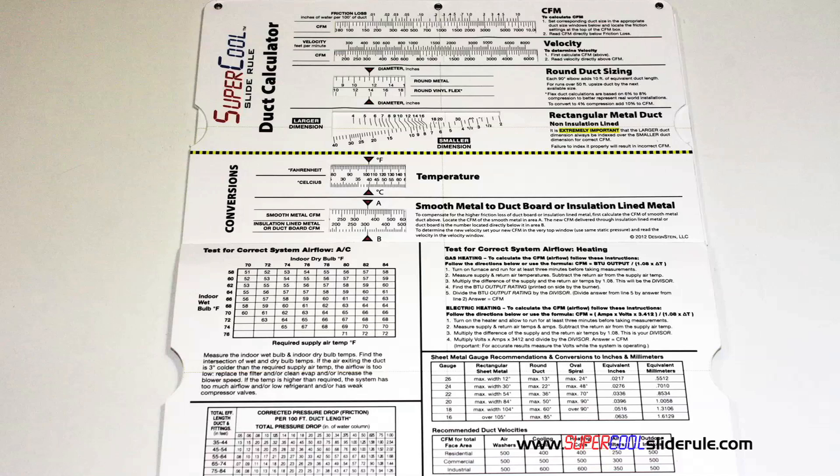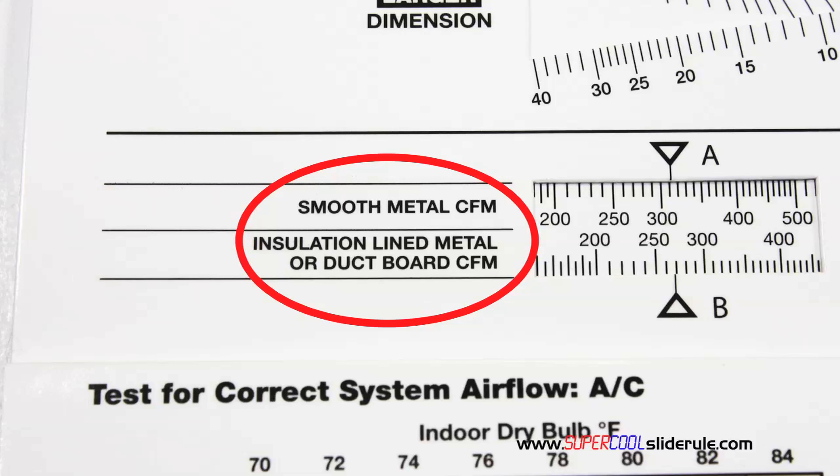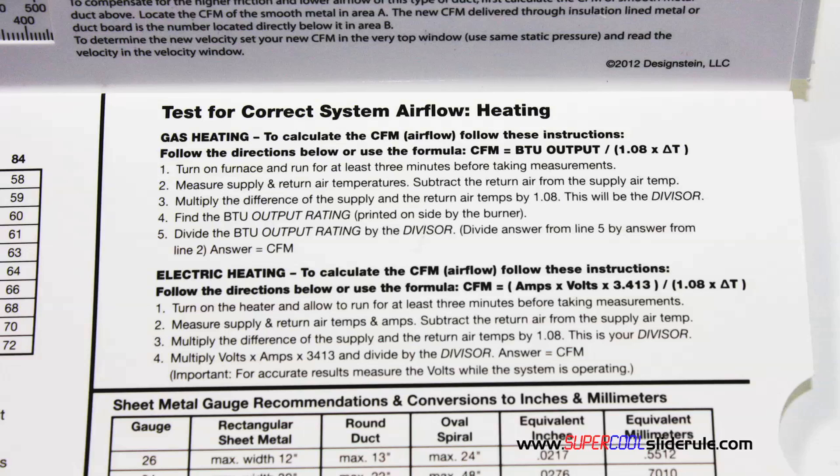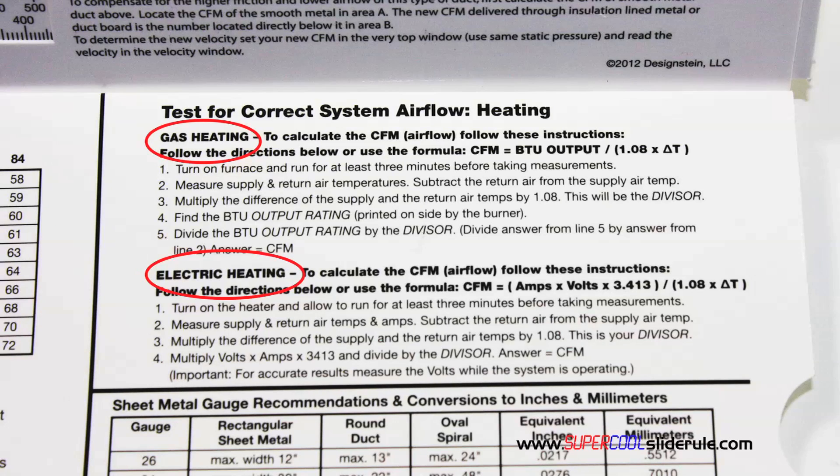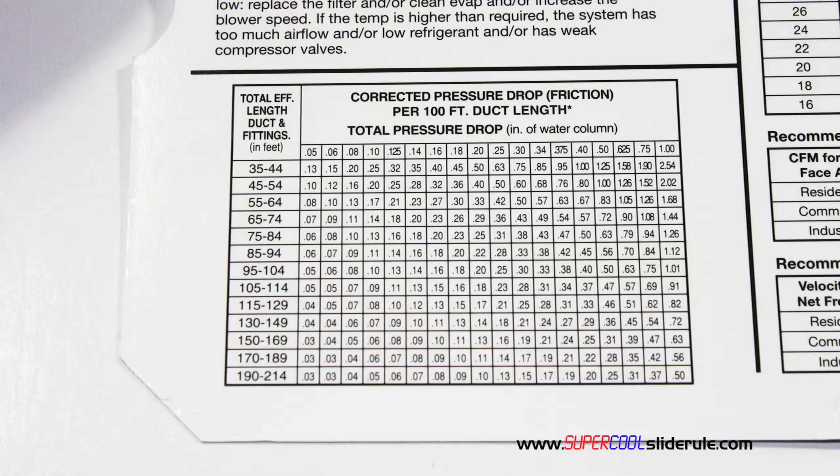Inside is packed with even more information. It performs sizing of both metal and flexible duct. It has the only direct reading conversion from smooth metal to insulation line metal we've ever seen. The majority of technicians have never been taught that if the insulation is on the inside of the ductwork you cannot size it with a regular duct calculator. It has step-by-step directions for determining airflow through a gas furnace, electric furnace, or an air conditioning unit.